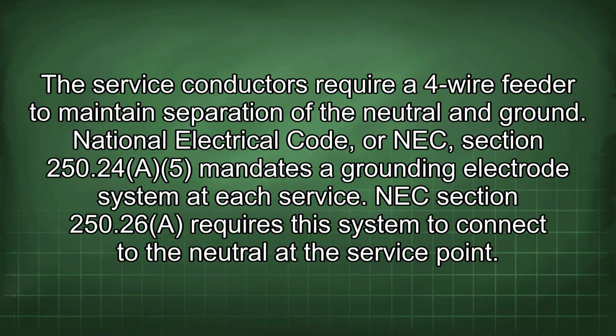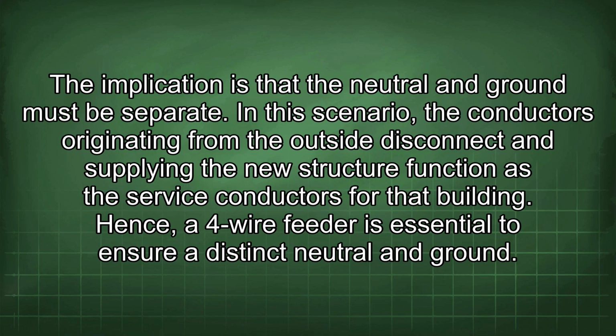Service conductors require a 4-wire feeder to maintain separation of the neutral and ground. National Electrical Code, or NEC, Section 250.24 mandates a grounding electrode system at each service. NEC Section 250.26 requires the system to connect to the neutral at the service point. The implication is that the neutral and ground must be separate.